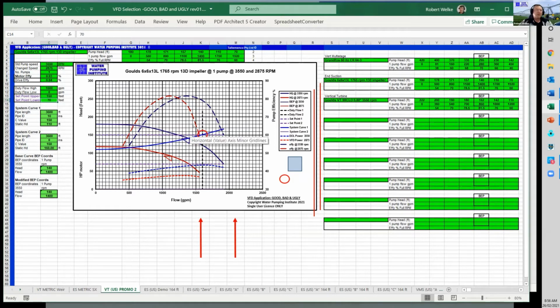Now we're going to fit a new pump to that point. So we're going down here to change the pump coordinates at the best efficiency point. C37 becomes 170. So you see the shape of the pump change. So we've just now created a new pump curve, and you can see that the best efficiency is fairly off to the left. And I deliberately have done this to show you what happens when certain pump configurations. C6 add 3030. So now the bottom performance curve, bottom duty, which is here, is satisfied with a pump speed of 3030.